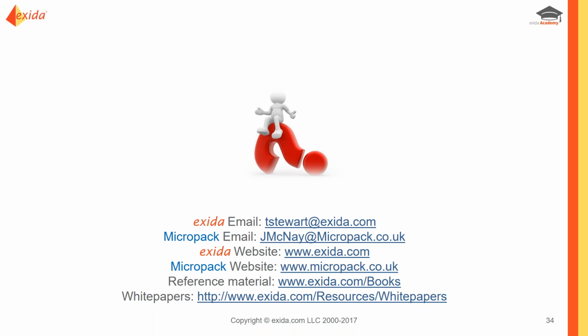And where that question's come from, I know that the methodologies associated with fire and gas mapping, and fire and gas mapping itself, was born out of offshore oil facilities. Micropack were involved with BP and Shell back in 1989 to develop the first fire and gas mapping tool, and that was primarily for application offshore. Now, recently, onshore facilities and even moving outside of oil and gas, we've had distilleries, waste recycling facilities, airports, aircraft hangars, all see the benefits of fire and gas mapping, because it allows that audit trail, and it allows you to know that the number of detectors you've specified is appropriate for the facility and the risks that you have on site. So it came from oil rigs, but it's certainly not just applied to oil rigs anymore.